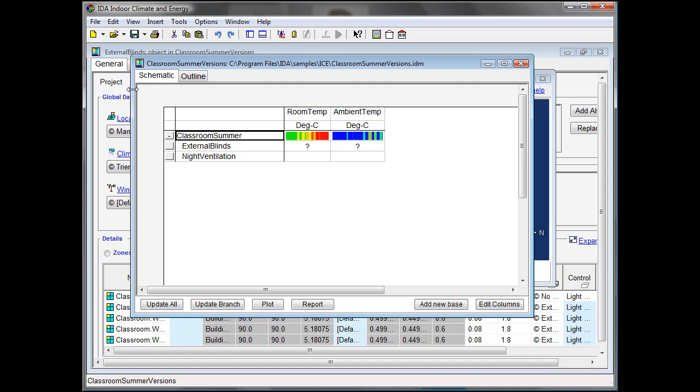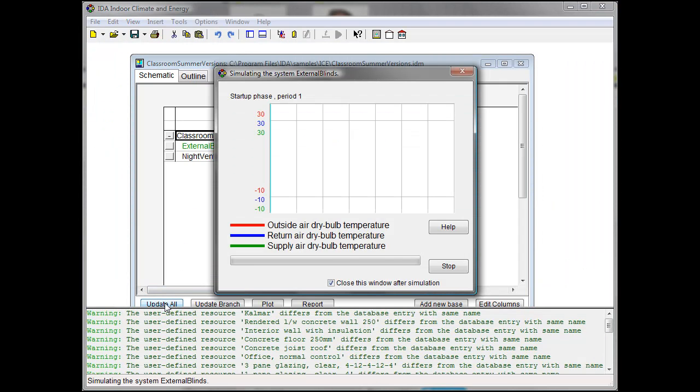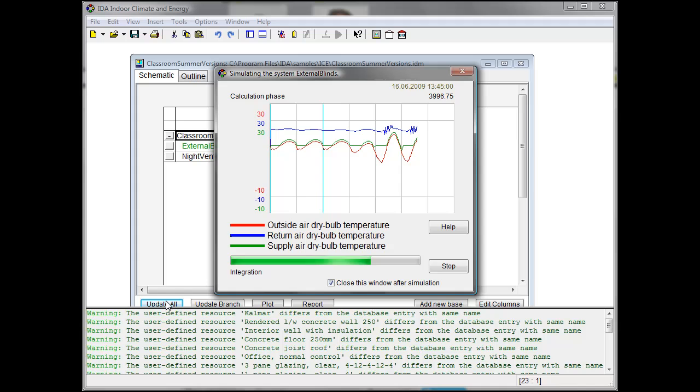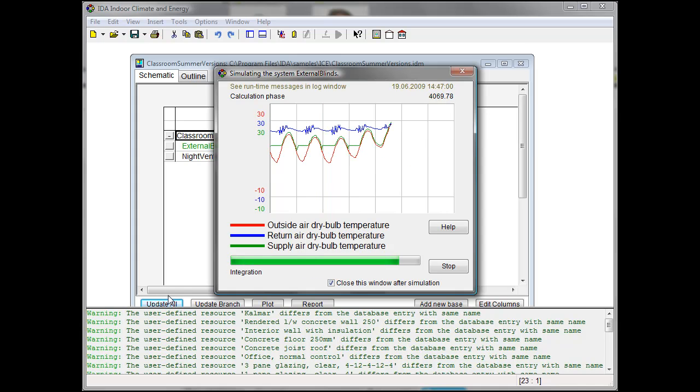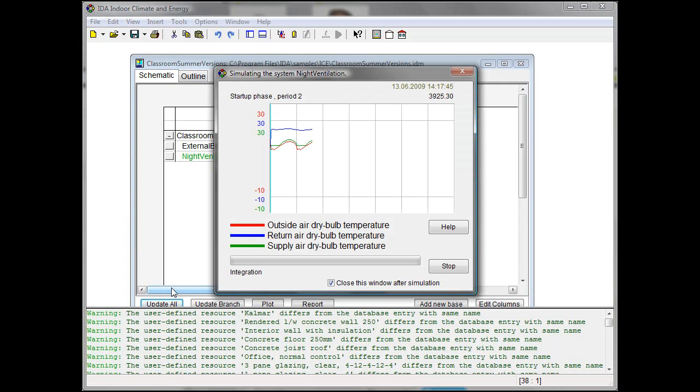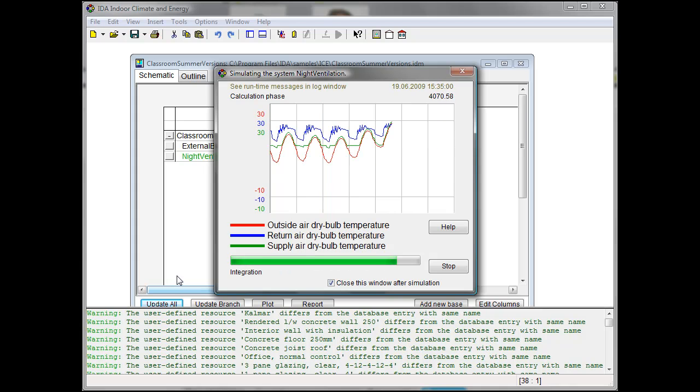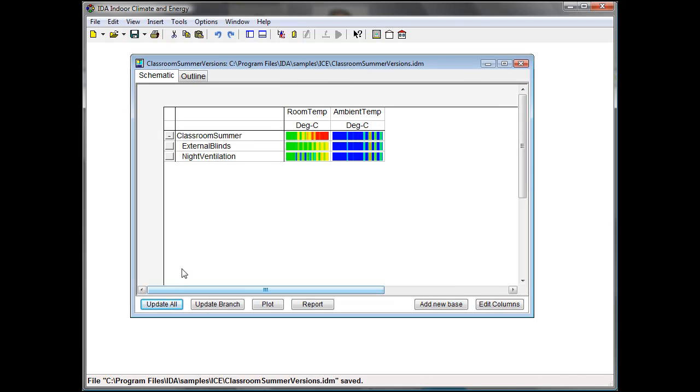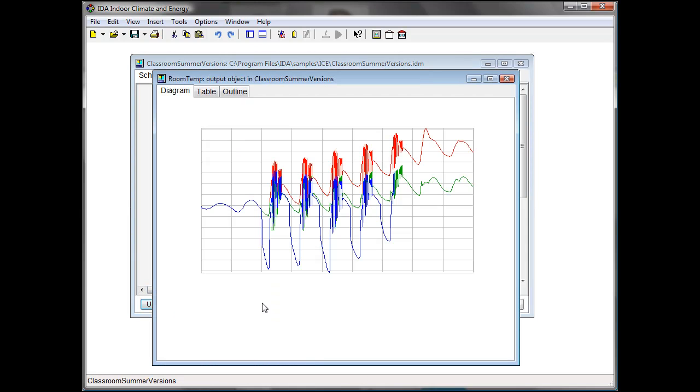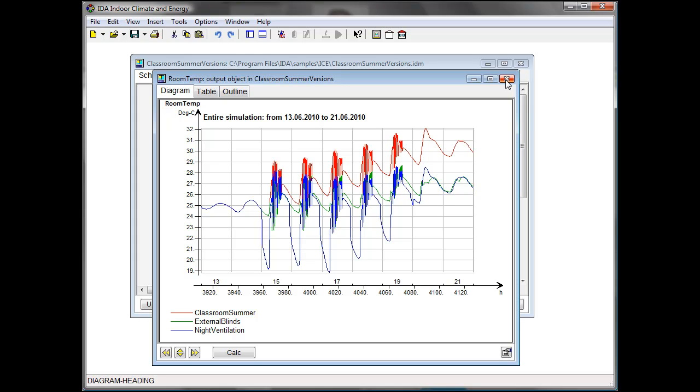Let's now update all cases. So IDA ICE will now simulate all cases which are modified and not simulated yet, which is the second with the external blinds and the third with the night ventilation. Let's now have a look at the results and compare the room temperature for all cases. And we can see that both versions show lower temperature, but still the temperature at the end of the week is higher than at the beginning of the week.